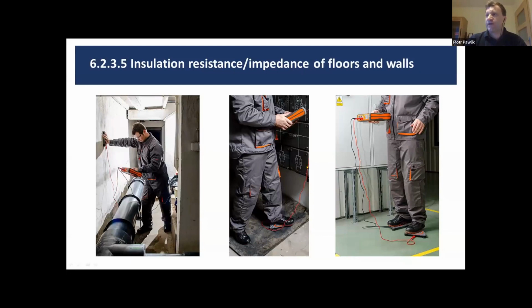Here we can see there's some electric panel. In front of it, there's the mat. So if there's a fault situation, this guy over here will not conduct the currents to the ground. He's standing on an insulating mat. So we need to check if this mat is working fine.